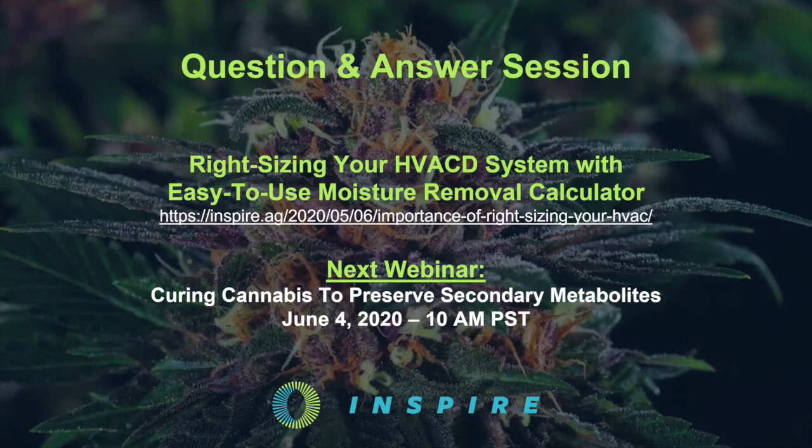But we use sensors that are accurate enough and have verified this with weighed product in the field, weighed over time, to know that our air conditioning system feeds back the moisture removal rate from the product itself. So we use our air conditioning system controllers to tell the growers and the harvesting team how much water is being lost on a pound per hour basis.